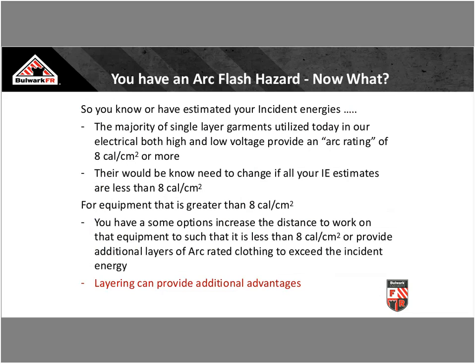So you have an arc flash hazard. Now what? Well, you've done a reasonable estimate of your incident energies on the utility side, or you've actually done your arc flash risk assessment on the 70E side. And what have you found out? You've found out in most cases a large majority of your equipment is going to be less than 8 calories of incident energy. That means if that piece of equipment fails, it's going to produce less than 8 calories of incident energy.